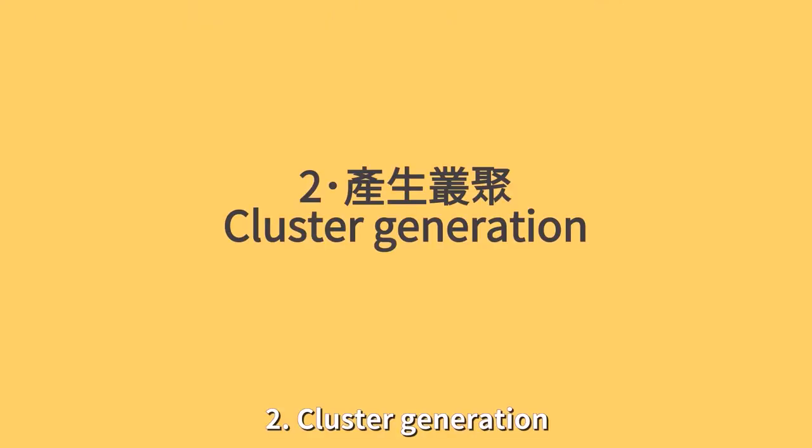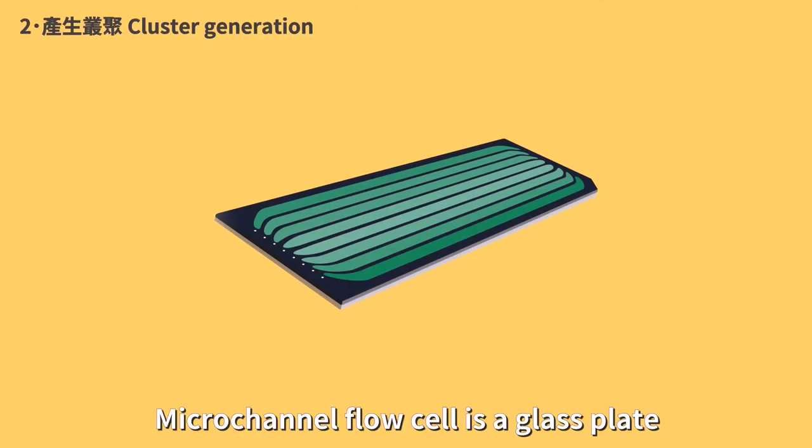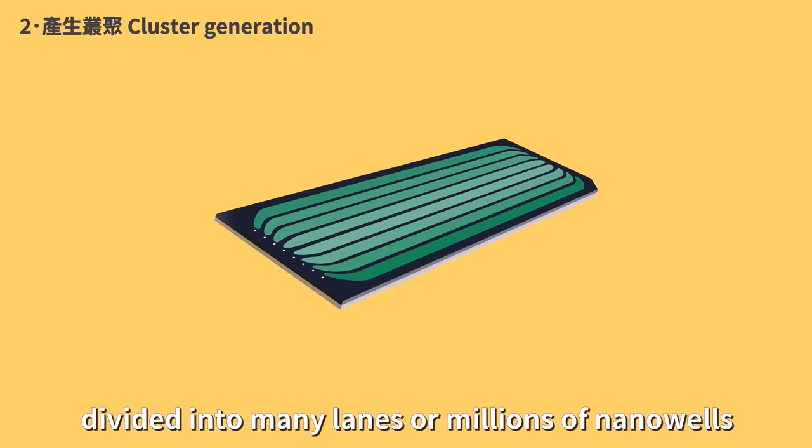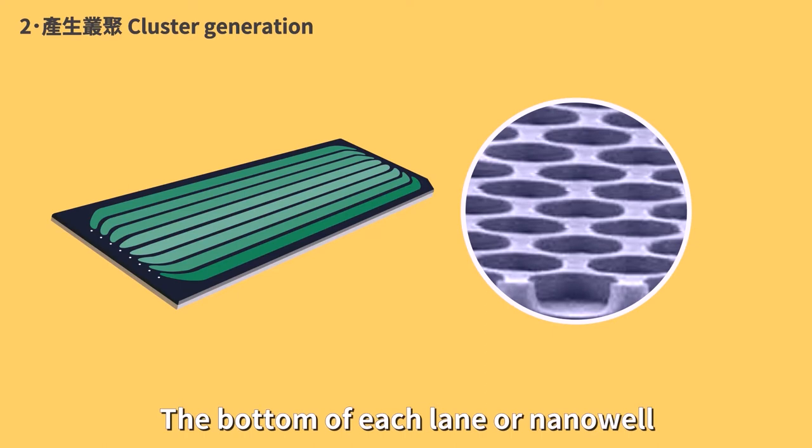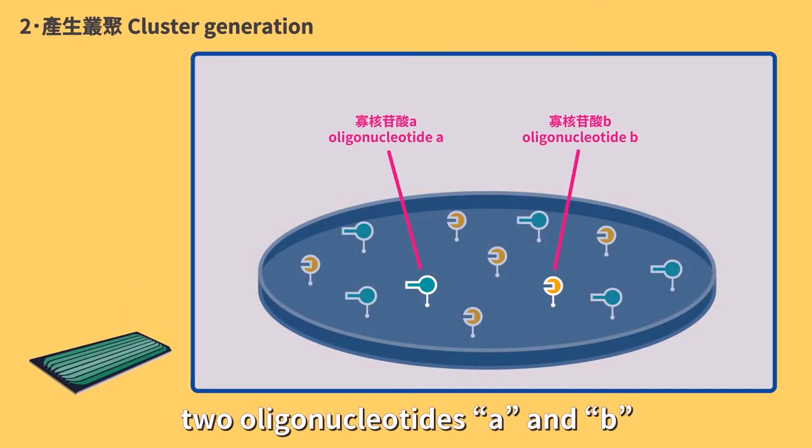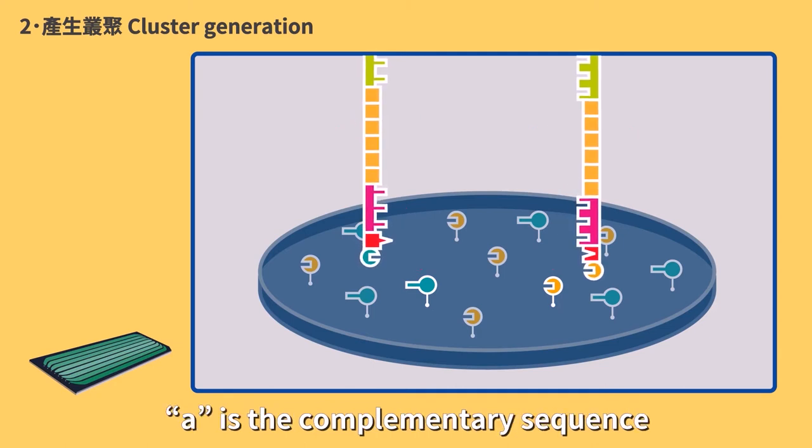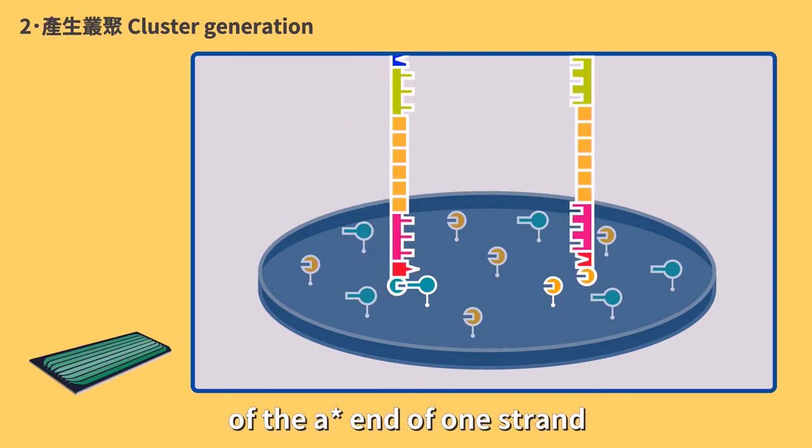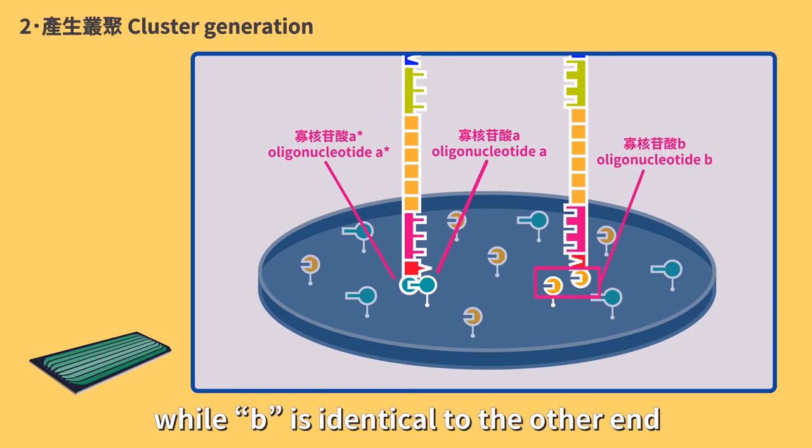Step 2: Cluster generation. Microchannel flow cell is a glass plate divided into many lanes or millions of nano-wells. The bottom of each lane or nano-well is evenly coated with two oligonucleotides, A and B. A is the complementary sequence of the A star end of one strand, while B is identical to the other end.